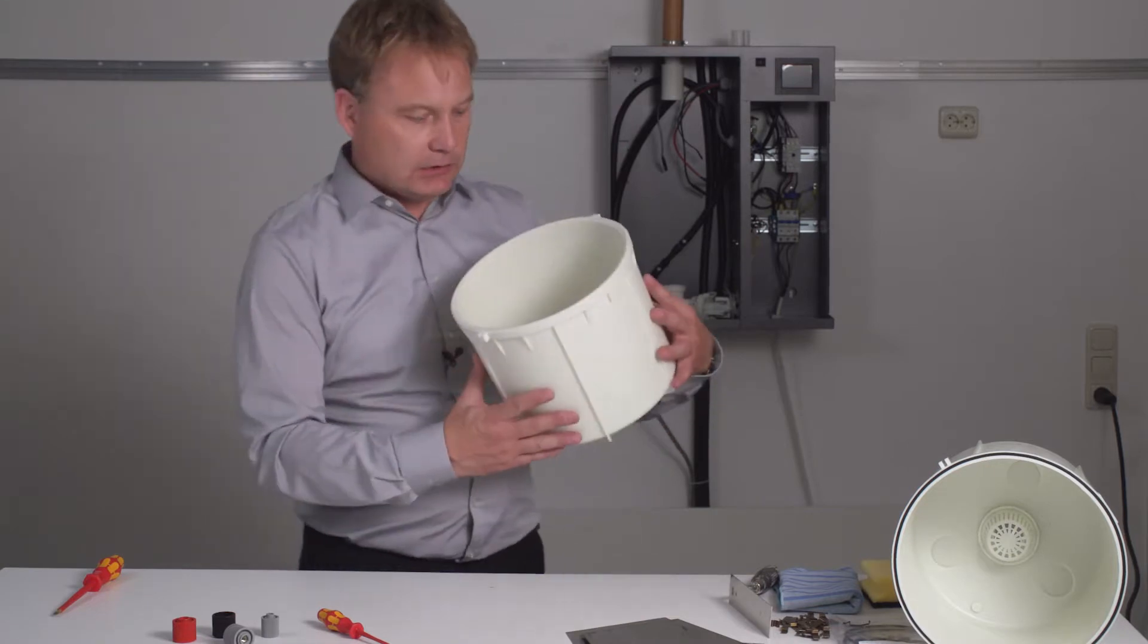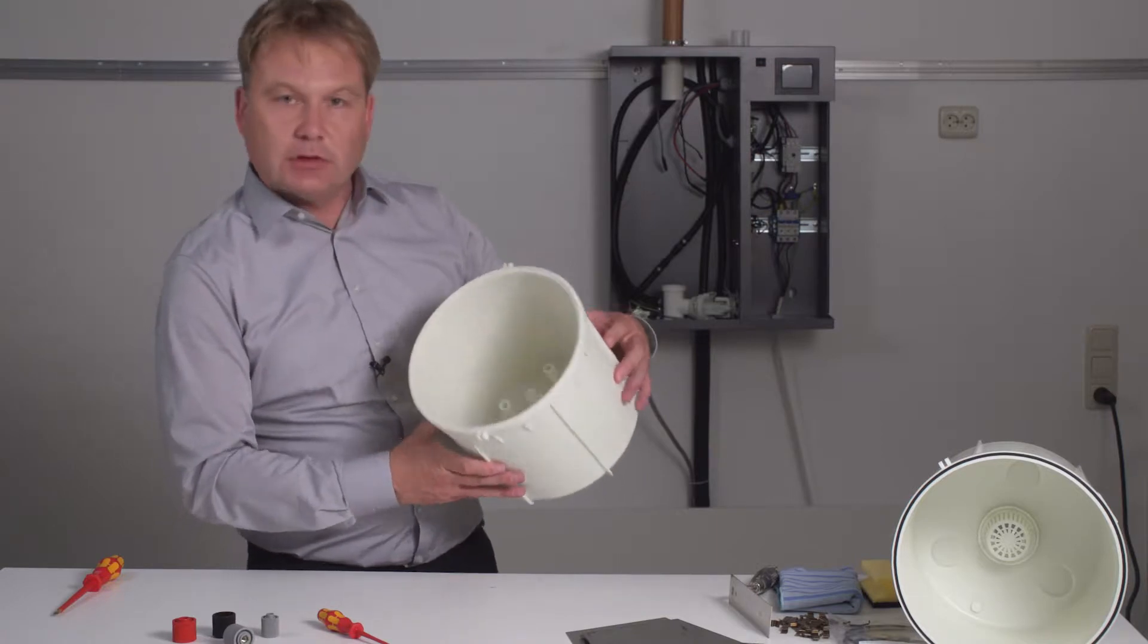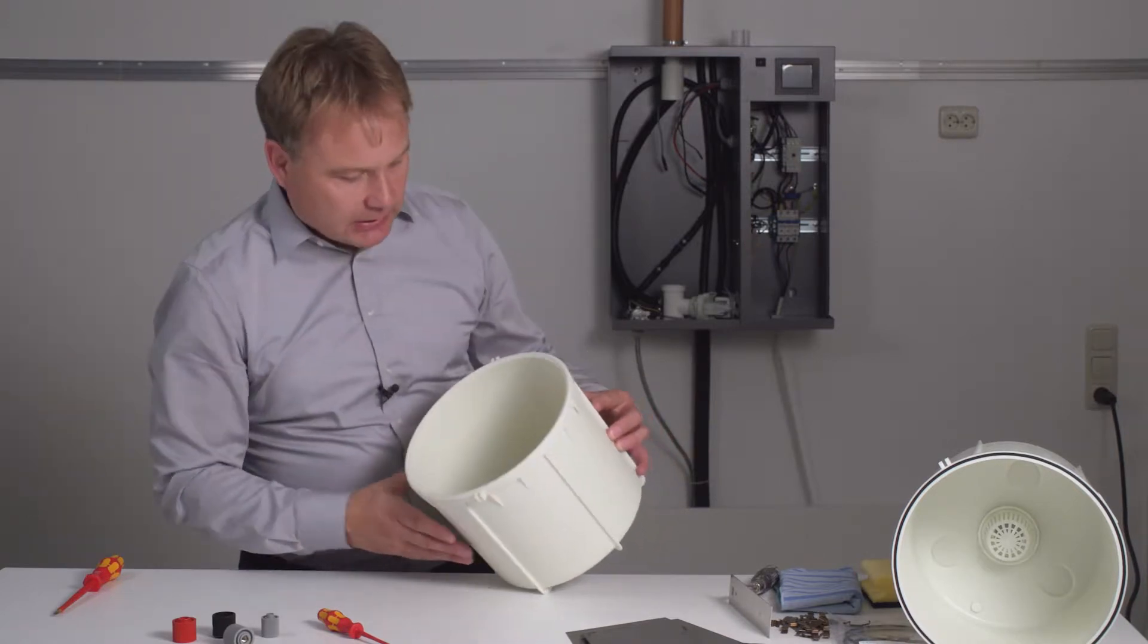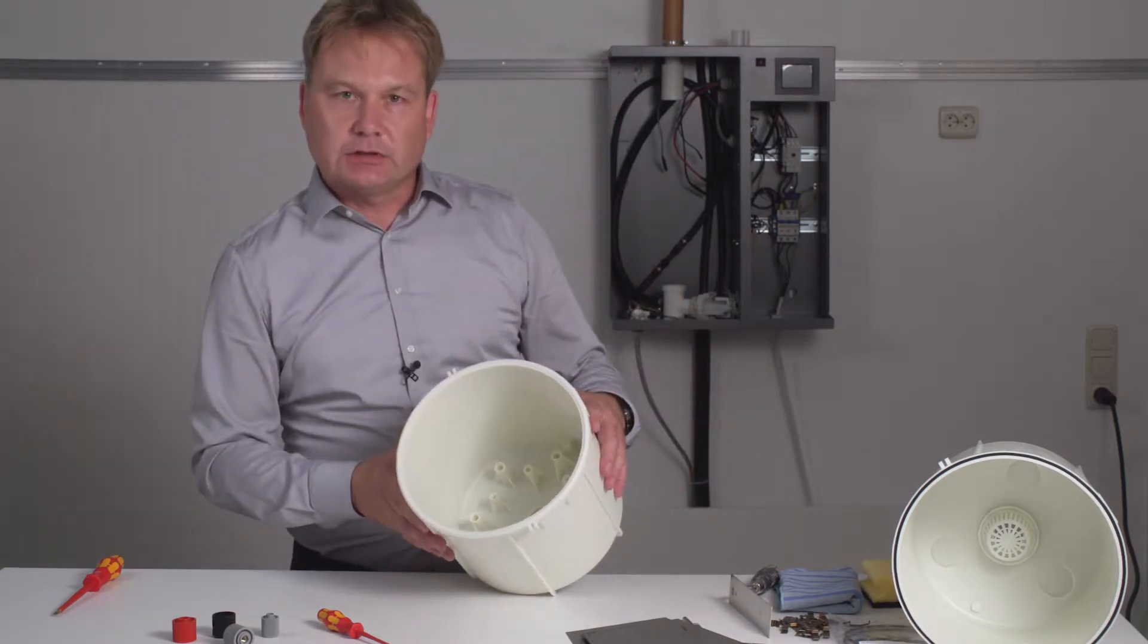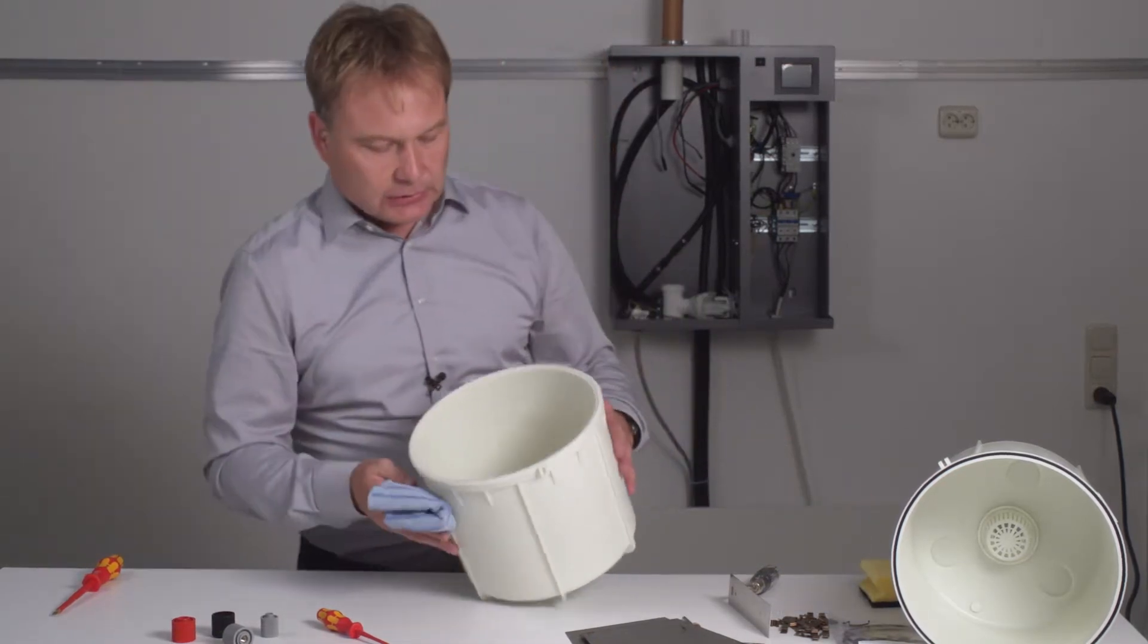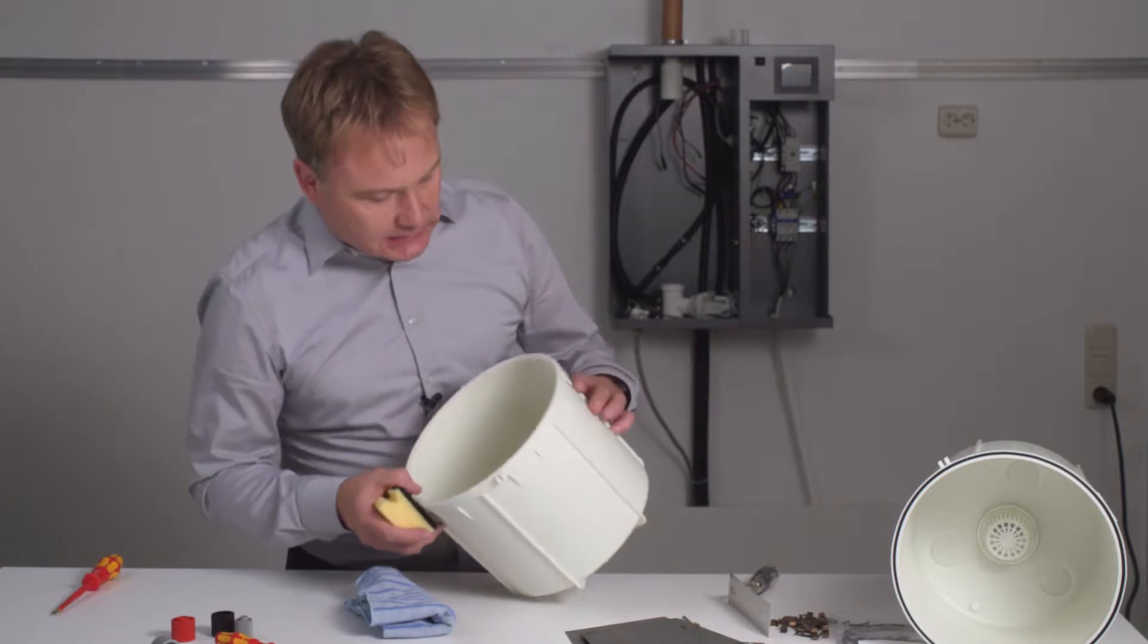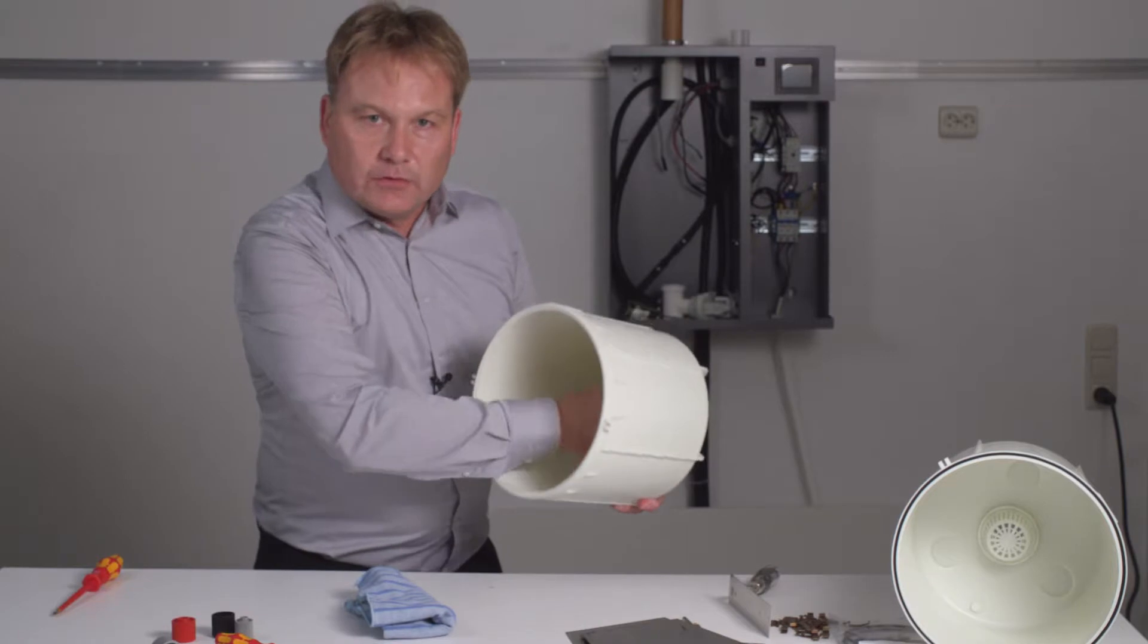Now I am able to clean the top half of the cylinder as well. Clean the cylinder top half even if you don't see any buildup. There can be unseen salt bridges that build up around the sensor electrode and can cause the unit to malfunction. Please clean with a normal rag. What also works well is a household sponge, the coarse colored side of the sponge. You can wipe around the sensor electrode to remove all possibly formed salt bridges.